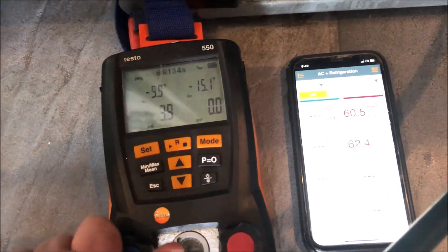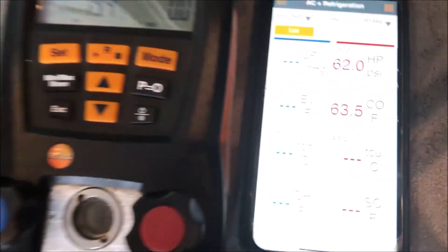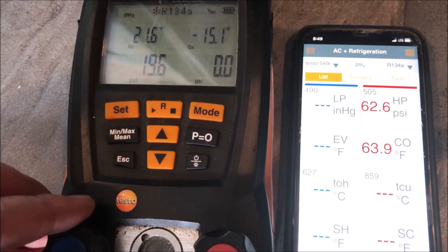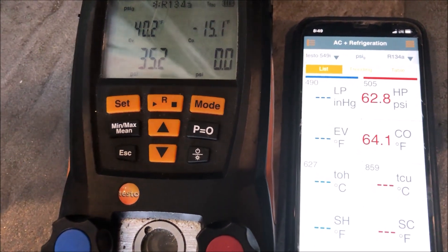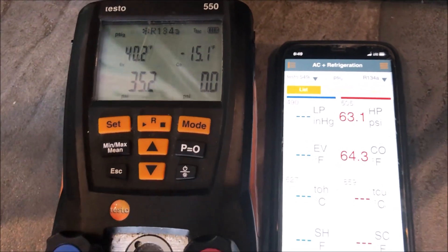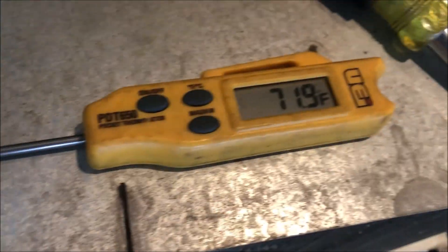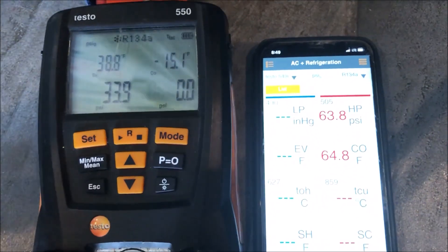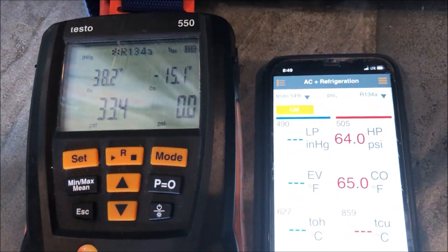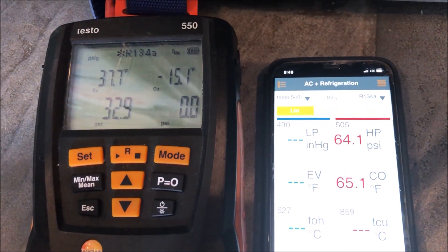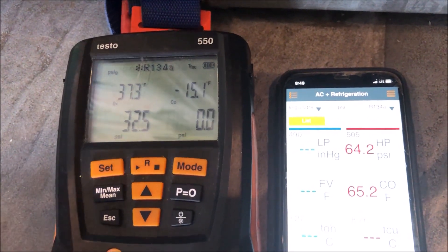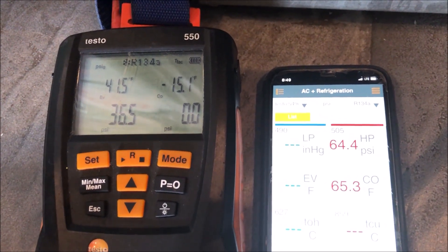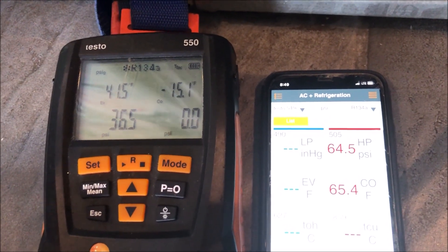And then pulling a good vacuum down to 500 microns. So we're all good there. Let's start recharging the system and let's just make sure we're not restricted again. We're gonna know right away because if we're pulling into a vacuum, the issue's there. So we're up to 72 Fahrenheit now. Let's just continue to charge here. We're gonna weigh in our 10 ounces and let's see if she pulls into a vacuum.